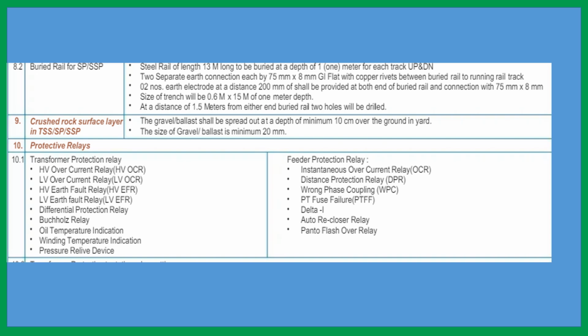The surface will be covered with gravel or ballast, spread to a depth of 10 centimeter over the ground in the yard. The size of the gravel ballast is minimum 20 millimeter. Each gravel or ballast will be 20 millimeter, and its thickness is a depth of minimum 10 centimeter. Sorry, 10 centimeter. And the relays provided in the TSS we know already.